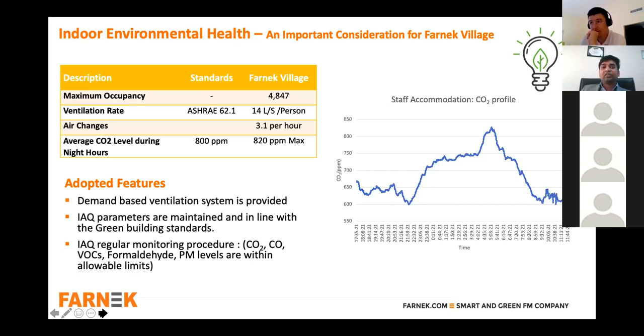A demand-based ventilation system is already in place for Farnek Village, where carbon dioxide is monitored continuously to ensure sufficient fresh air for the inmates. IAQ parameters are monitored on a periodic basis, and most are well within allowable limits per various standards. In the table, we can see the ventilation rates and corresponding standards. We are providing a ventilation rate of approximately 14 liters per second per person, whereas the minimum requirement per ASHRAE standard is around 2 to 3 liters per second per person, and 0.3 liters per second per square meter.